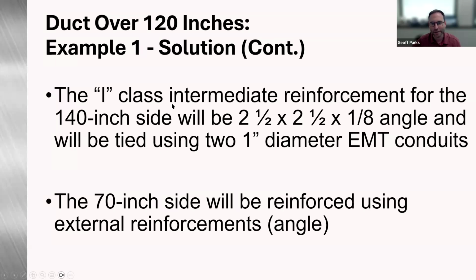And then our I-class intermediate reinforcement for the 140-inch side is going to be a 2.5 by 2.5 by 1/8 inch angle. That was sized using table 2-29. And then this intermediate angle will also be tied using 2 1-inch diameter EMT conduits, because remember, when building over 120, the joint and the intermediate reinforcement needs to be backed up with tie rods.